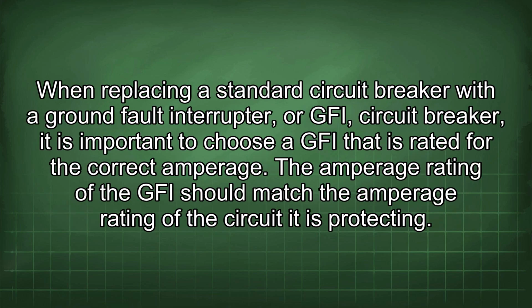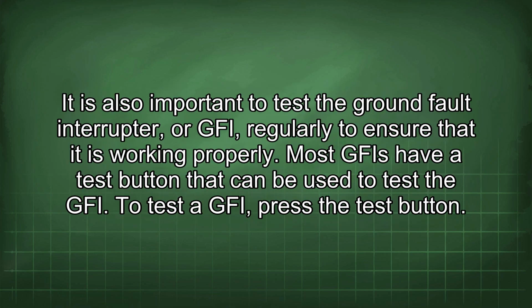When replacing a standard circuit breaker with a ground fault interrupter, or GFI, circuit breaker, it is important to choose a GFI that is rated for the correct amperage. The amperage rating of the GFI should match the amperage rating of the circuit it is protecting. It is also important to test the ground fault interrupter, or GFI, regularly to ensure that it is working properly.